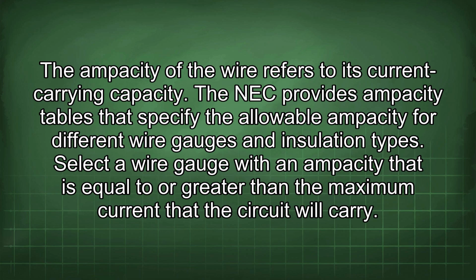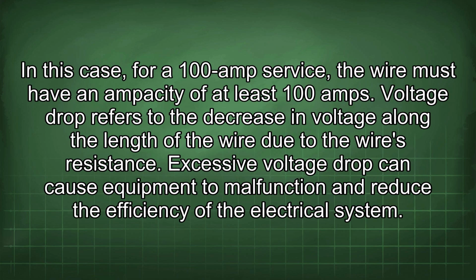The ampacity of the wire refers to its current carrying capacity. The NEC provides ampacity tables that specify the allowable ampacity for different wire gauges and insulation types. Select a wire gauge with an ampacity that is equal to or greater than the maximum current that the circuit will carry. In this case, for a 100 amp service, the wire must have an ampacity of at least 100 amps.